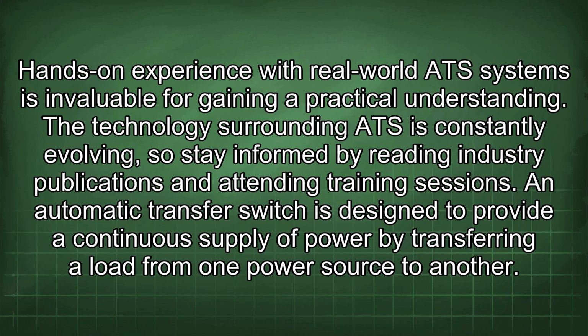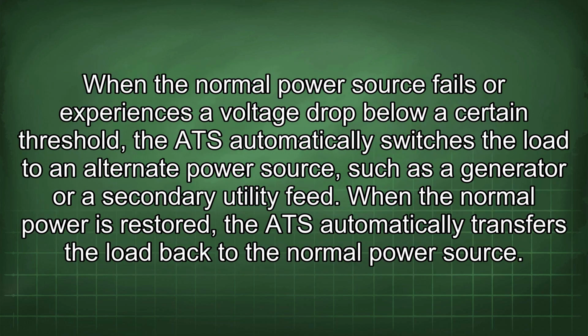An automatic transfer switch is designed to provide a continuous supply of power by transferring a load from one power source to another. When the normal power source fails or experiences a voltage drop below a certain threshold, the ATS automatically switches the load to an alternate power source, such as a generator or a secondary utility feed. When the normal power is restored, the ATS automatically transfers the load back to the normal power source.